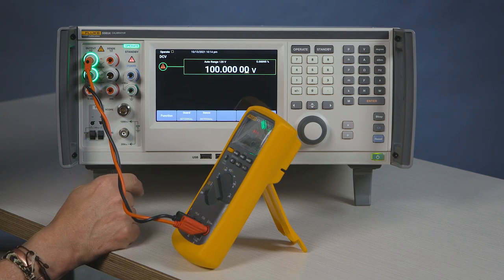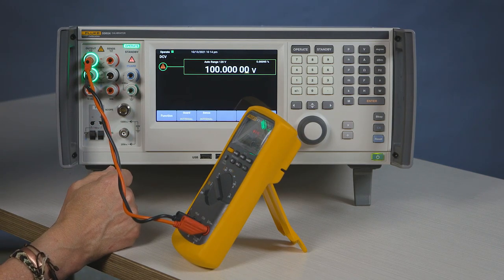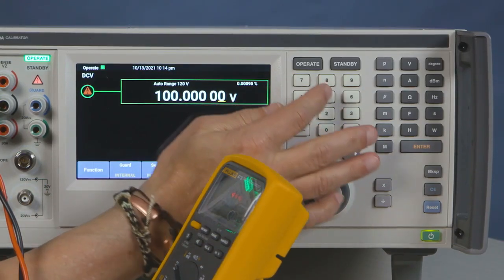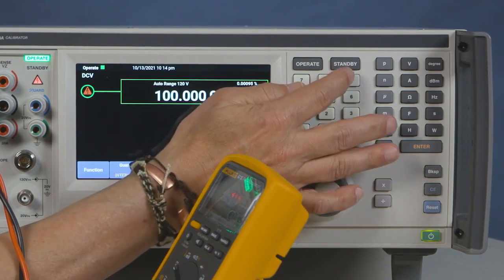Press operate. Now you're engaged into the 100 volt range. At that point, you're done with the calibration. Just press standby.